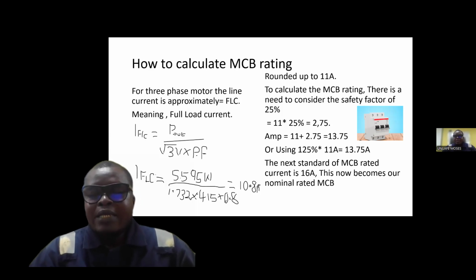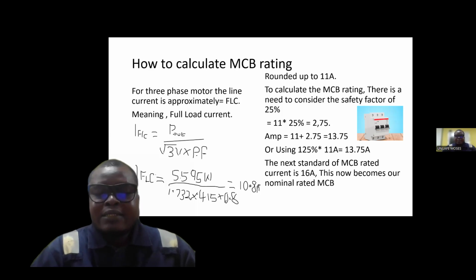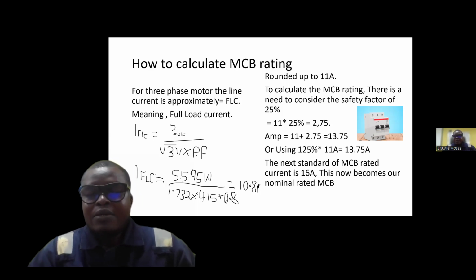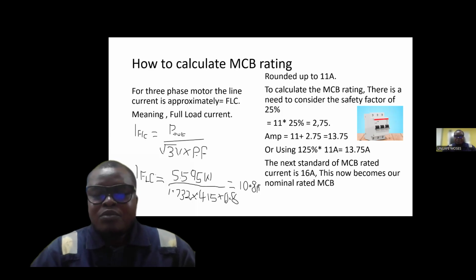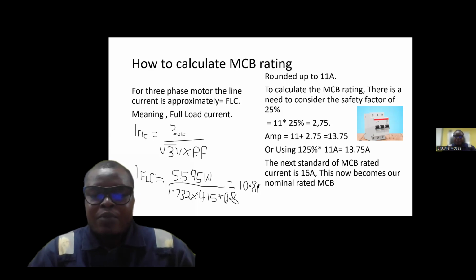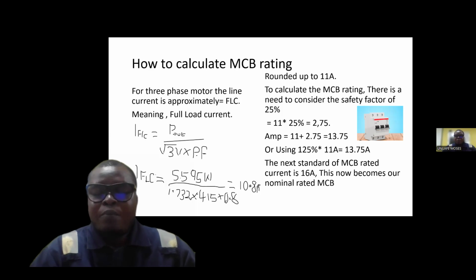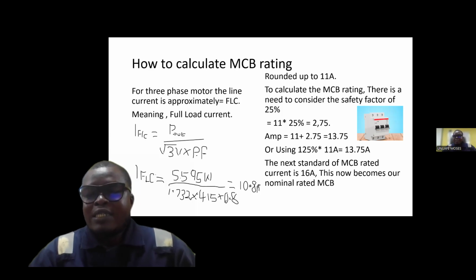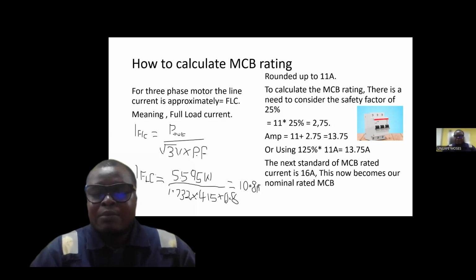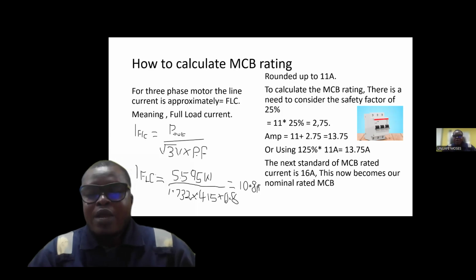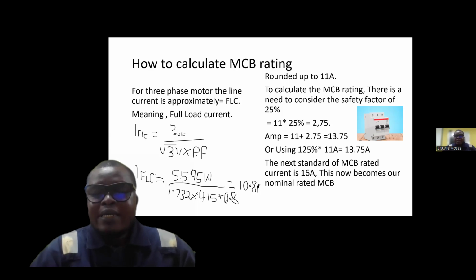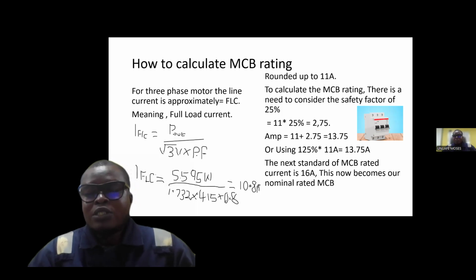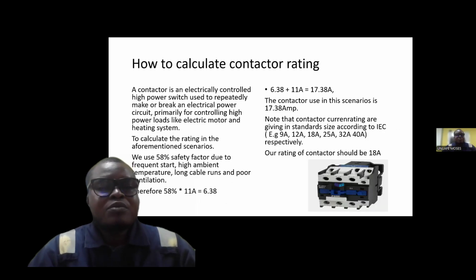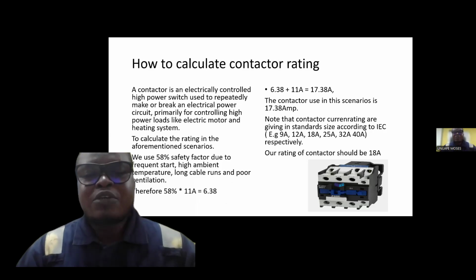So 13.75 amps now becomes the standard MCB rating. Now, MCB ratings are arranged in standard according to IEC as 16 amps, 32 amps respectively. The next amperage that you need to pick after having this 13.75 amps is 16 amps. So therefore, we have our nominal rated MCB to be what? 16 what? Amps.